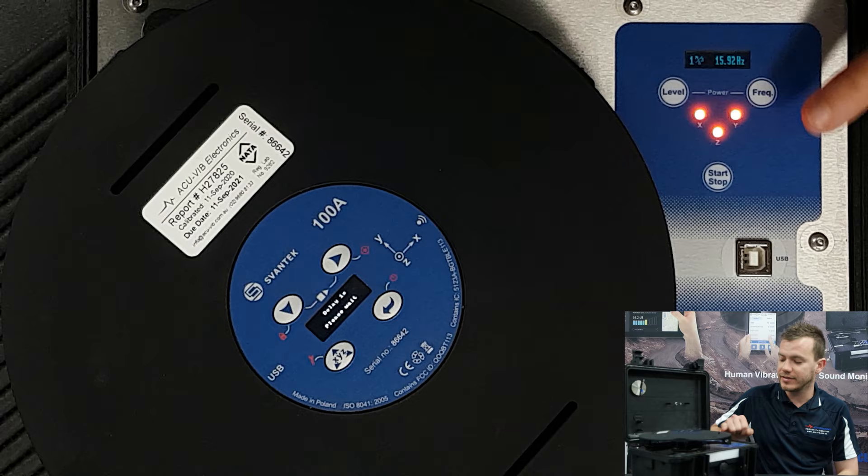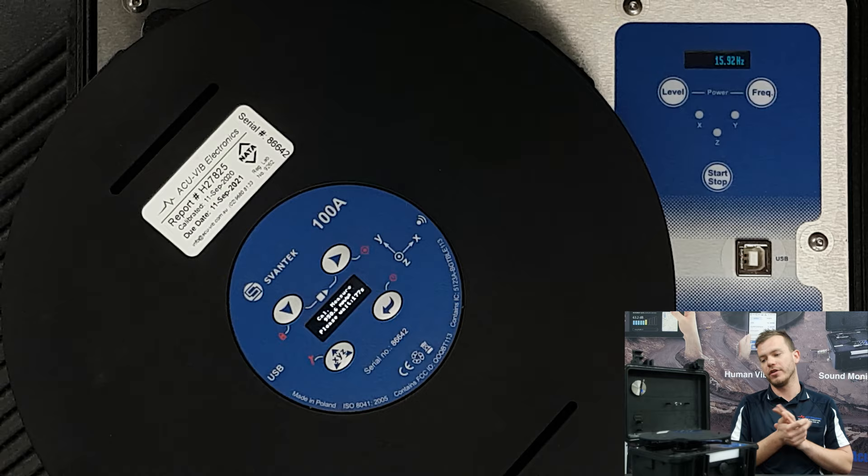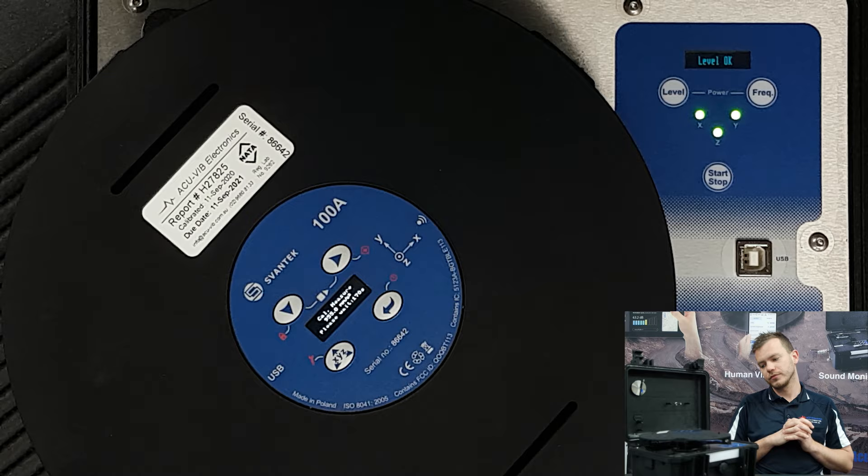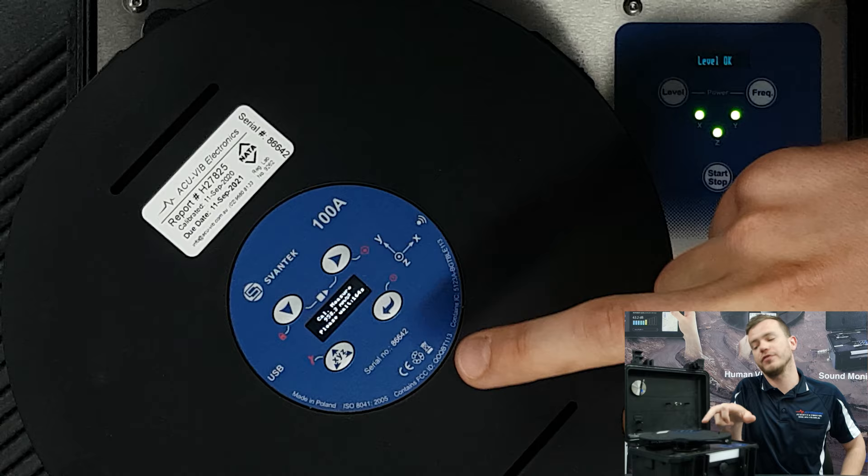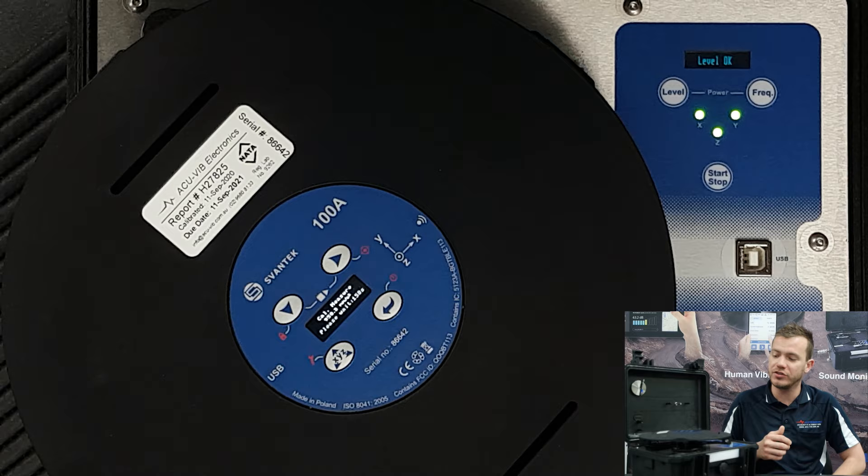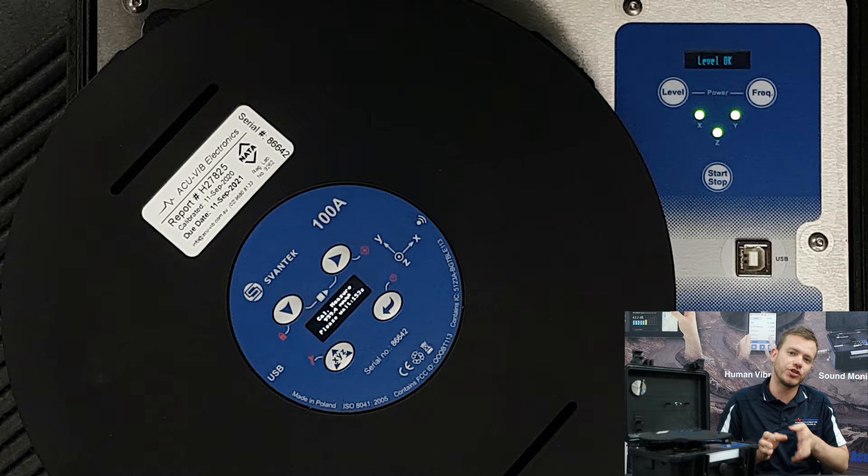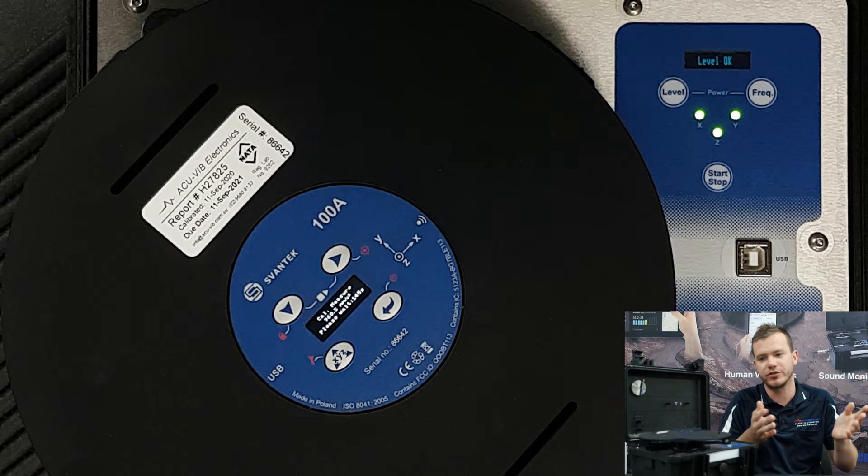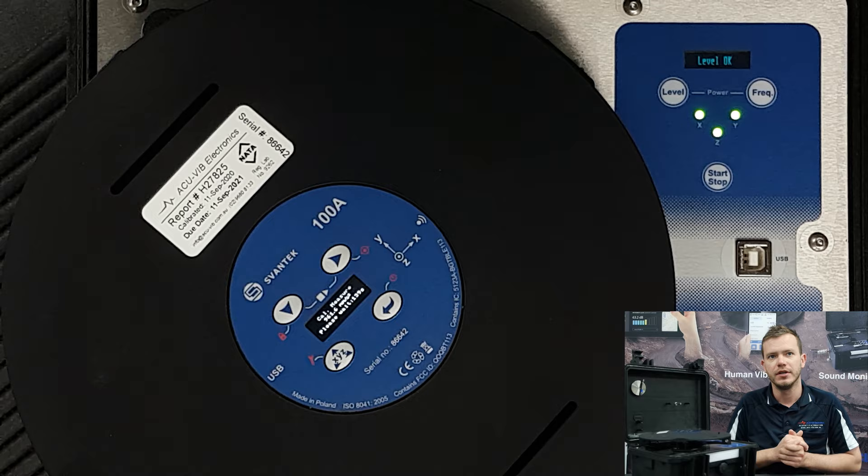We press enter and I'm going to press start on the shaker. You can see the three X, Y, Z axes are leveling, so try to stay away from the table or the tile while it's doing this. As you can see it's leveled okay now and we're going through the internal calibration of the SV100A. It's got 160 seconds. In the manual it says repeat this test up to three times - these are periodical calibrations. The in-situ check is more of a verification before and after a measurement, but for periodical calibration they say repeat it a couple of times to make sure the cal factor goes down as low as possible.